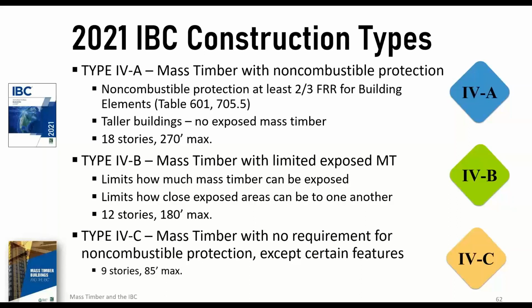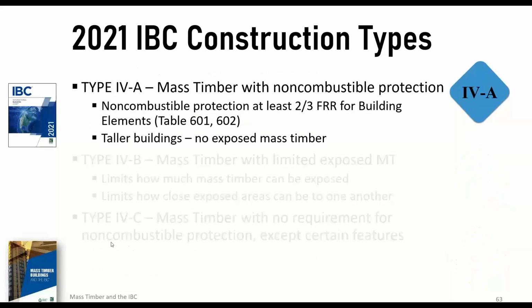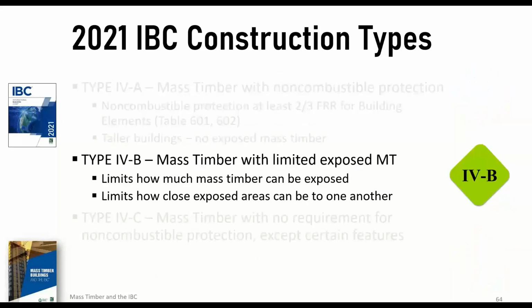Certain features, plenum, stuff like that, hoistways have to be protected inside and out with at least one layer of 5/8 Type X, but you can go a little bit higher than the existing 6 stories currently permitted in the IBC, but unfortunately we're still capped out at a conservative 85 feet. So maybe there'll be a future code change a couple cycles down the road, but at this point, fully exposed mass timber is maximum 9 stories and 85 feet, still with a 2-hour fire resistance rating.